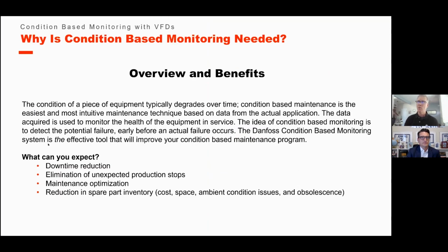The overview: why is condition-based monitoring needed? The condition of a piece of equipment typically degrades over time. Condition-based maintenance is the easiest and most intuitive maintenance technique, based on data of the actual application. So the data acquired is used to monitor the health of the equipment in service. The idea of condition-based monitoring is to detect the potential failure very early in the process, before the actual failure occurs. This is very unique.